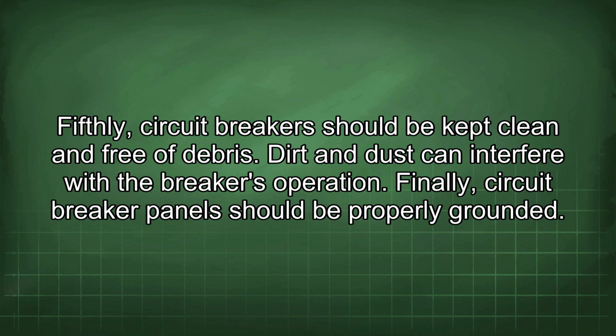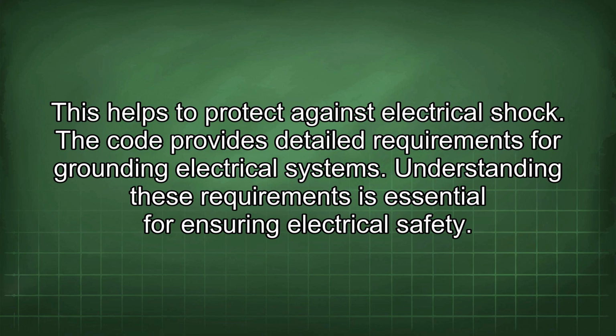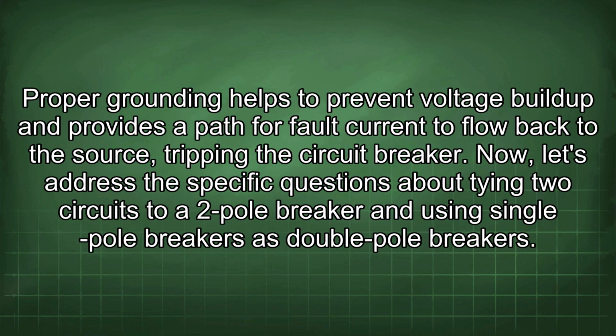Finally, circuit breaker panels should be properly grounded. This helps to protect against electrical shock. The code provides detailed requirements for grounding electrical systems. Understanding these requirements is essential for ensuring electrical safety. Proper grounding helps to prevent voltage buildup and provides a path for fault current to flow back to the source, tripping the circuit breaker.